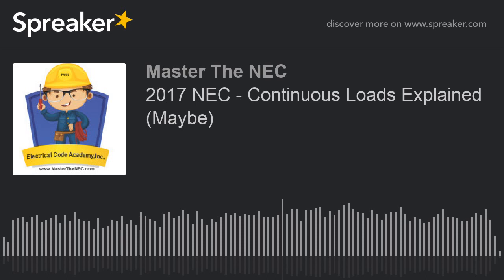And again, you need to go watch Derating Demystified at youtube.com/masterthenec to get a more in-depth understanding of it. But we can use the value that's in the 90 degree column provided the conductor's insulation value meets those that are in this table. That means the rating is 90 degrees rated. Okay? All right, so we're doing that. Now, we can only use that 90 for these adjustment and correction purposes. So what do I mean when I say adjustment and corrections? All right, let me not go there yet.